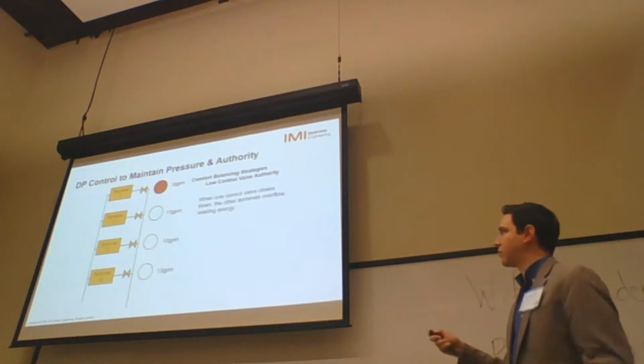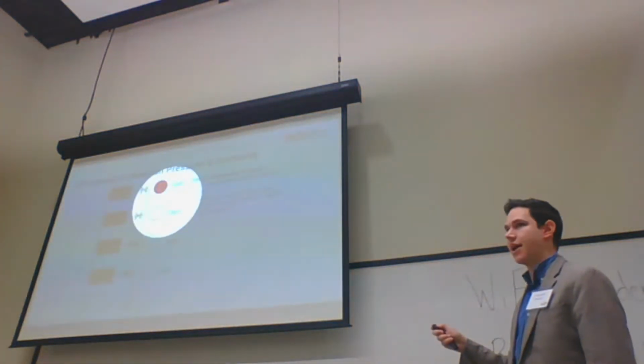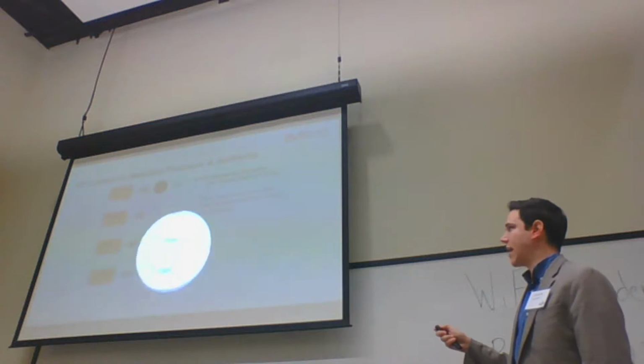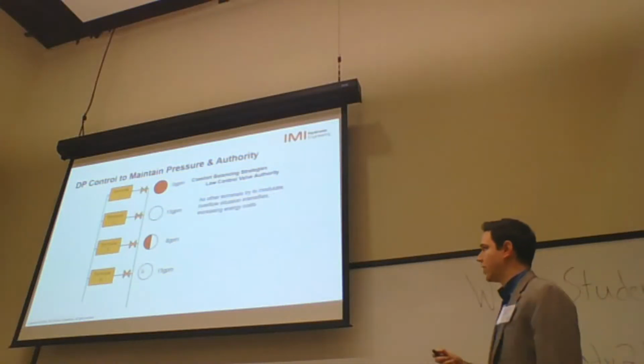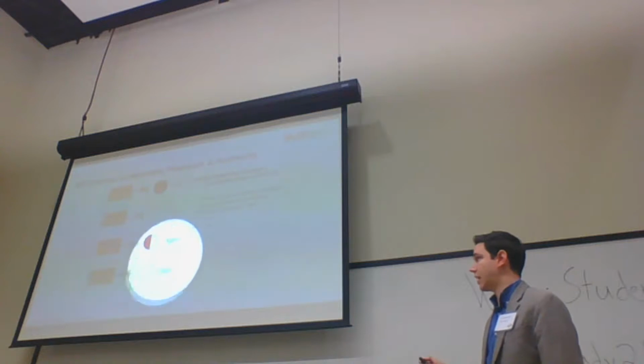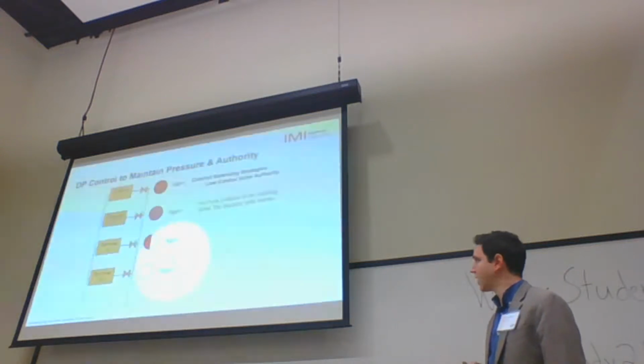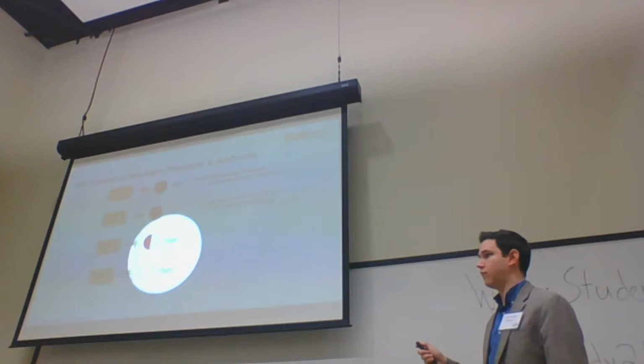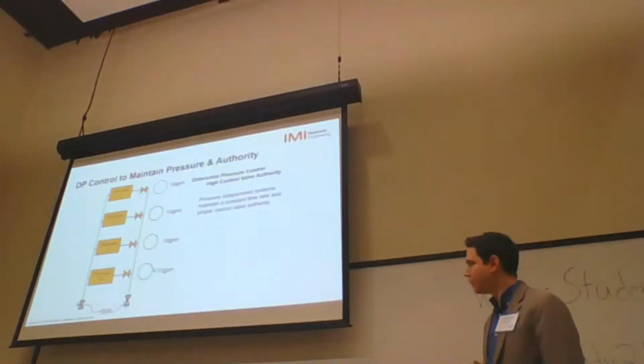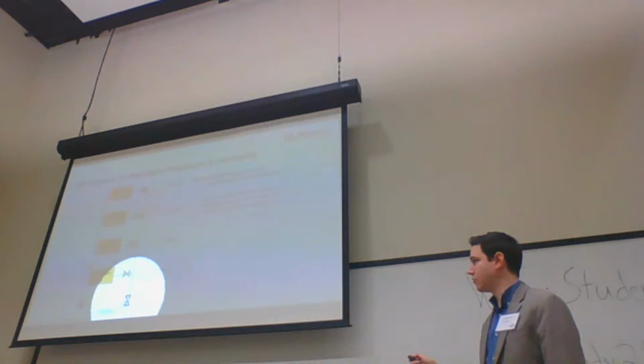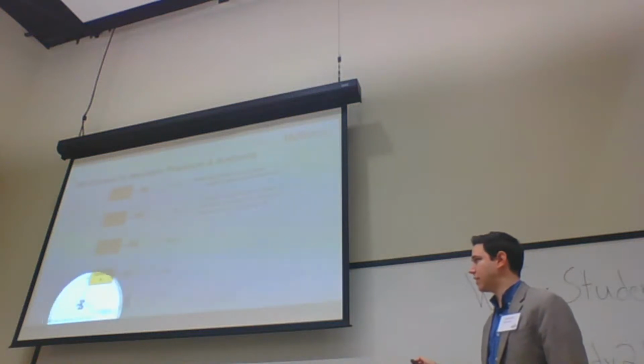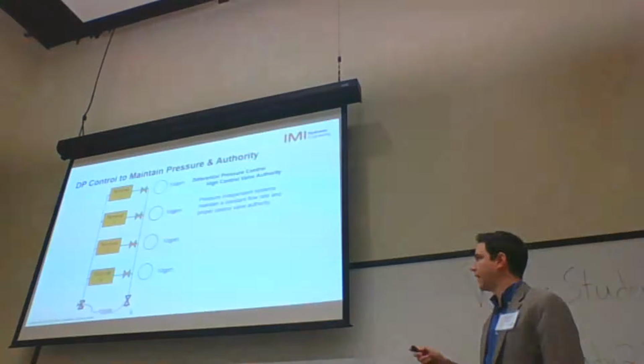If I'm closing the last one of my system, and I have only manual balancing valves, you're going to have overflow. So instead of 10, now I'm getting 13 GPM in each coil. If I'm closing this by 50% and now getting 8 GPM, I'm getting a higher overflow in the others. If I'm closing the third one, or the second terminal unit, I'm getting a huge overflow for the other two that are still open. With a differential pressure controller in the branch, that is a pressure independent stabilization per se.